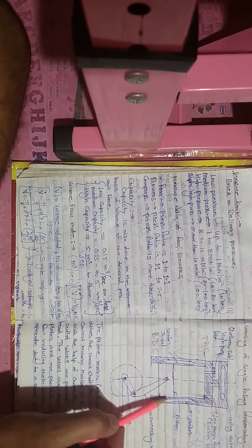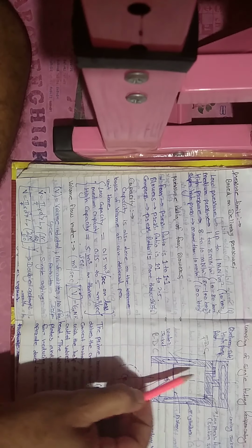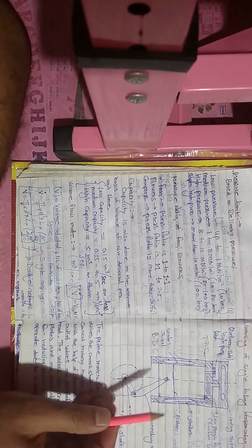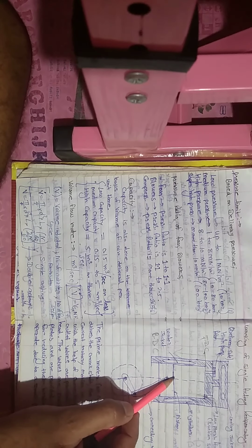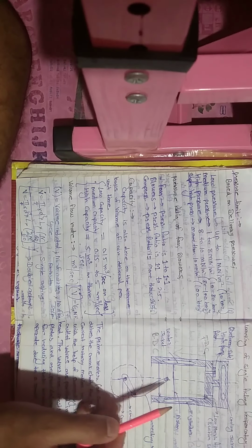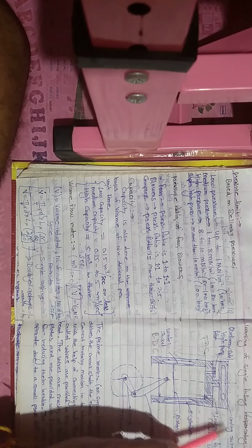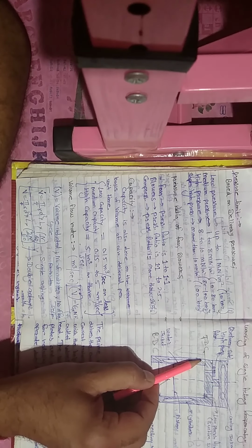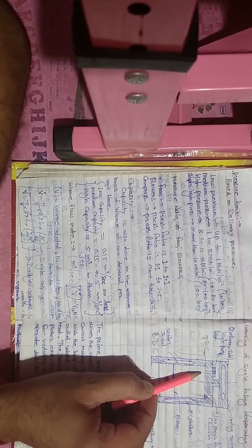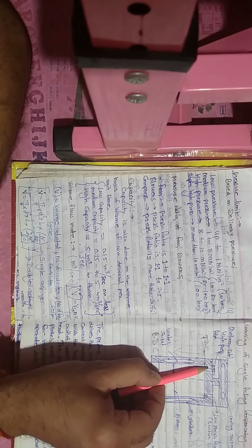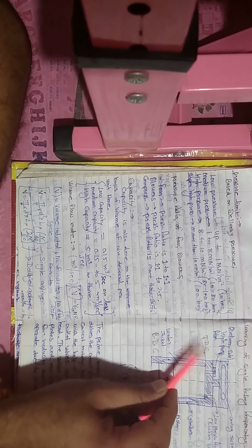When the piston moves from bottom dead center to top dead center, both the valves are closed and the compression of air is carried out. During compression heat is liberated, which is rejected from the outer surface of the cylinder, so the cooling jacket is provided. At the end of compression the pressure of air is high, and when the piston reaches top dead center, the delivery valve opens due to the high pressure difference.